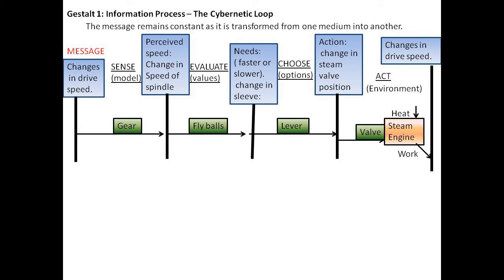The governor then needs to choose from the available options. With the lever, there are two options called negative and positive feedback. Positive feedback is when the lever translates a rise in the sleeve into an increase in the valve opening. Negative feedback is when the lever translates the rise in the sleeve into a decrease in the valve opening.